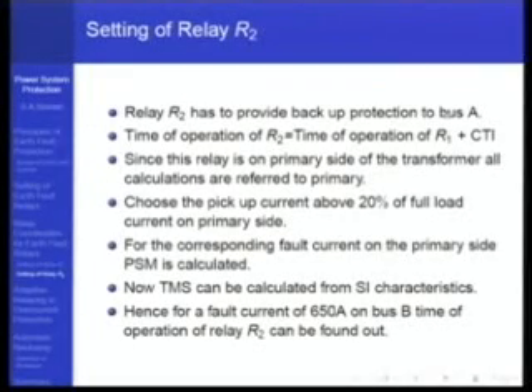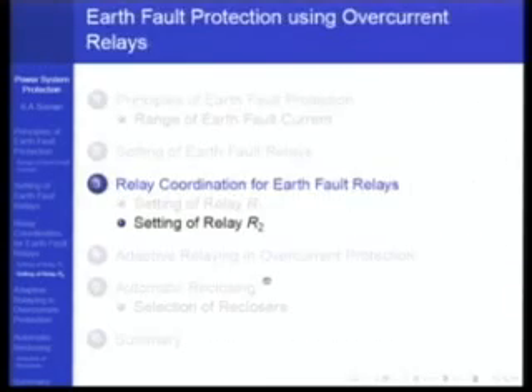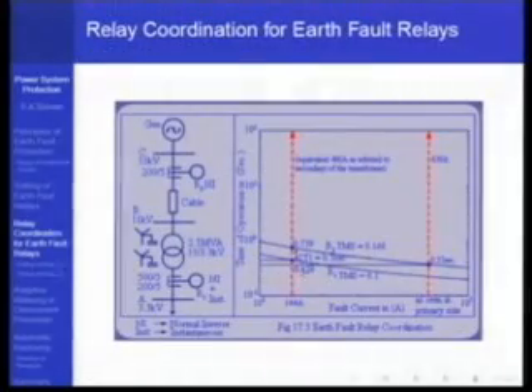The setting of relay R2 has to provide backup to bus A. The time of operation of R2 has to be the time of operation of R1 plus CTI. Since this relay is on the primary side of the transformer, all calculations are done with respect to the primary side. Choose a pickup current of about 20% of the full load on the primary side. For the corresponding fault current on the primary side, PSM is calculated, then TMS, and so on. One thing to note on the x-axis is that the fault current is all referred to the primary side. Because I am doing coordination, this relay is doing protection on the secondary side and that one is doing protection on the primary side.